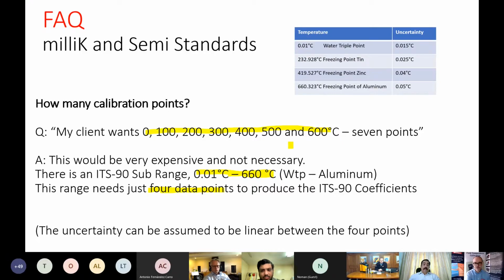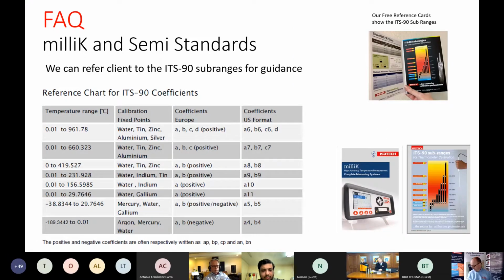So we can say to the customer, you might need to cover that range, but really, this is a metrology instrument, high quality instrument, high quality resistance thermometer. You can follow the ITS90, and the ITS90 tells us we need just 4 points. And to make life easy, we've got a chart here with the different temperature ranges, which points we calibrate at, and which coefficients that we get. In Europe, we tend to just call them A, B, C, D, positive and negative. In the US, it's more commonly to call them A6, B6, C6. It's the same thing. It's just a terminology and how we refer to the coefficients.